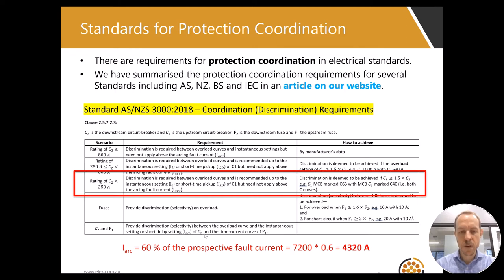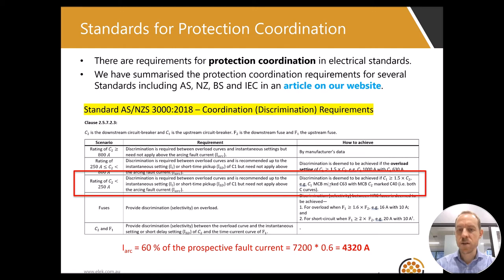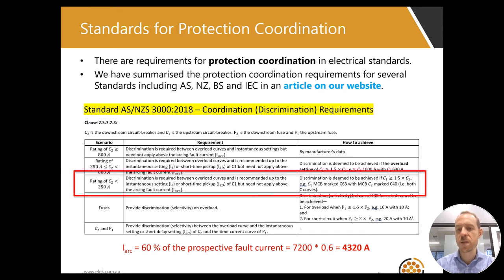The arcing fault current is defined as 60% of the prospective fault current, which in our example is 4320 amps. The table states to achieve compliance, discrimination is deemed to be achieved if the rating of C1 breaker is greater than or equal to 1.5 times the rating of C2.